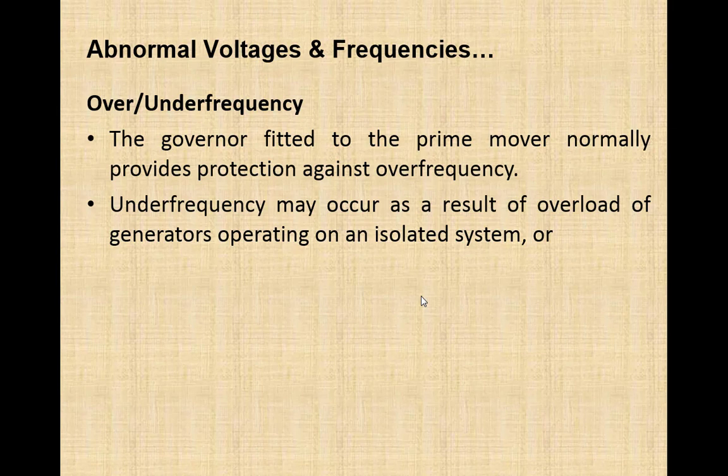So overloading means the prime mover is unable to meet the requirement of electrical load. So immediate attention is required to provide protection against this overload condition. So it means in generator, instead of monitoring the current, frequency is the parameter that would be detected in order to determine overload condition.